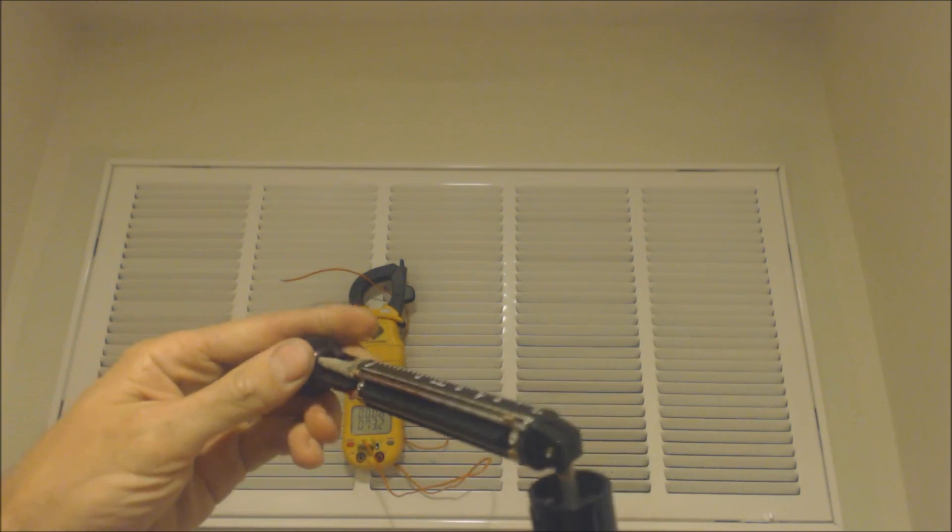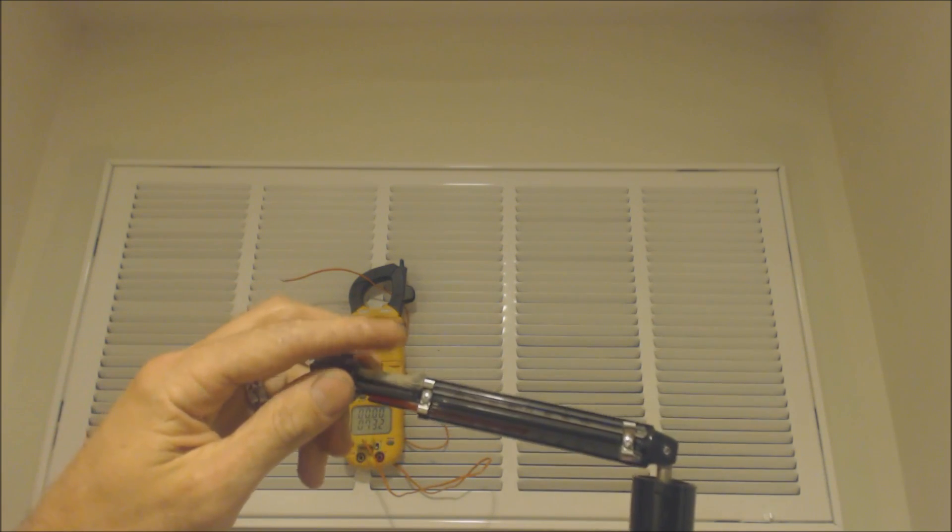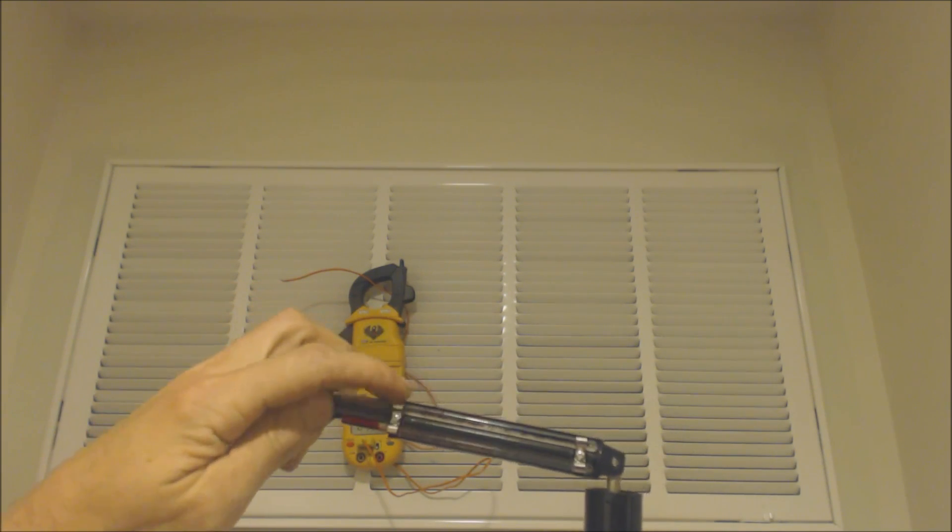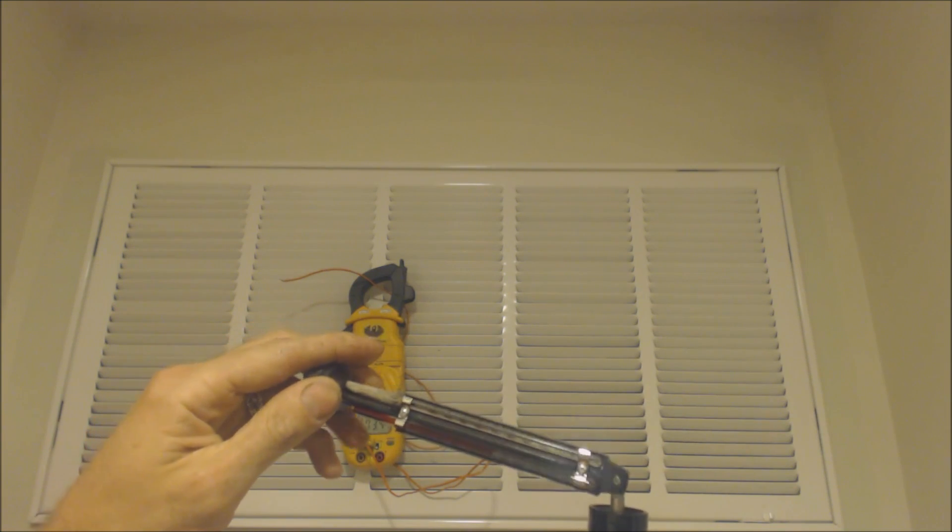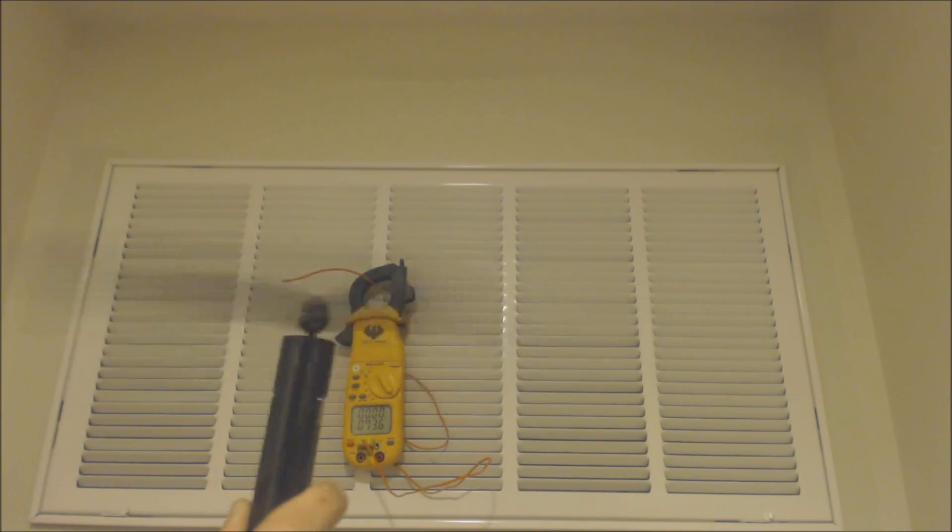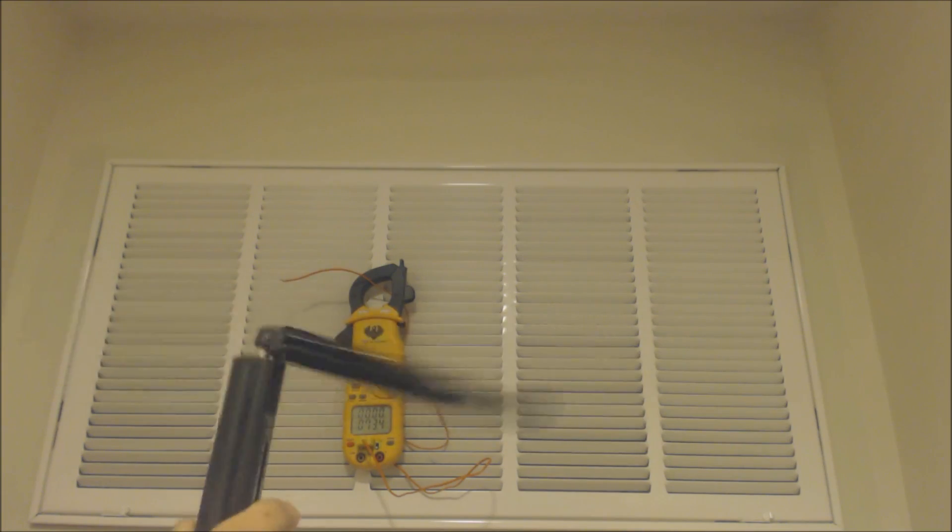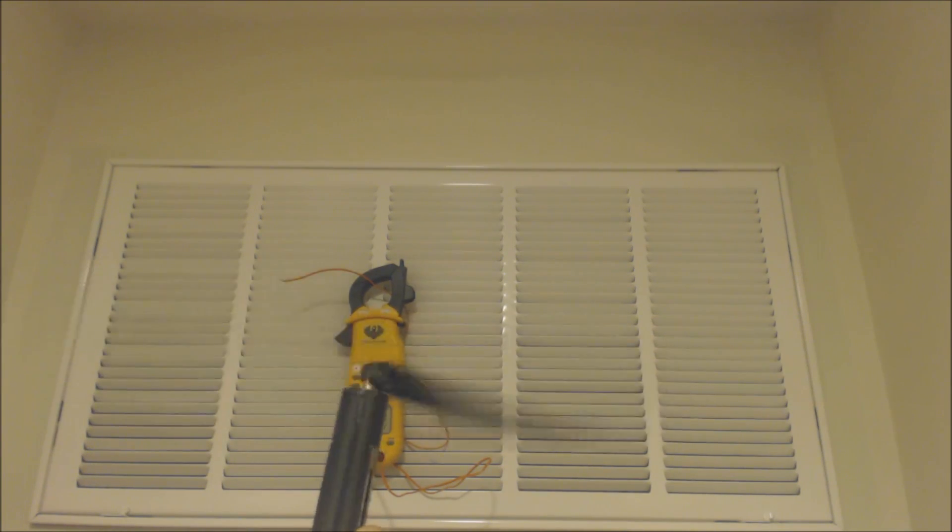Our sling psychrometer here has a wet sock on the end of a mercury bulb thermometer. As that's slung around, you're going to swing it around for about two minutes in order to read your wet bulb temperature. What's happening is that wet sock is actually cooling the bulb down to get an accurate temperature reading.